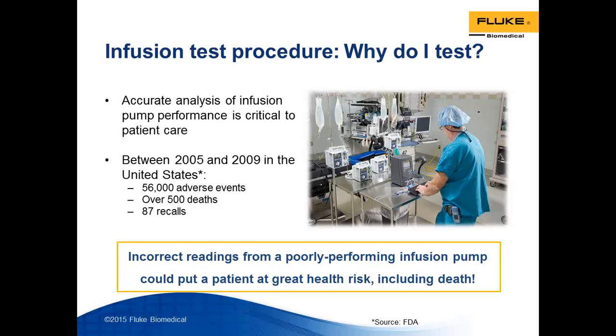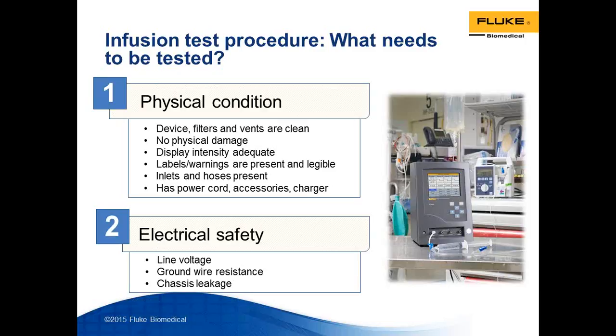So essentially, I think we all know that incorrect readings from an infusion pump that is not performing as specified can put a patient at great risk, including death. So it's very, very critical that infusion pump testing be taken very seriously. Now, what does that entail? How are infusion pumps tested? Generally speaking, organizations either go with their internal protocol, or more commonly seen, they go with what the manufacturer specifies be tested for any specific infusion pump.